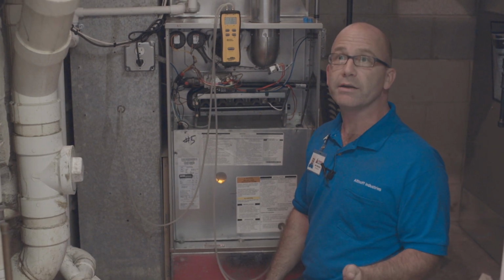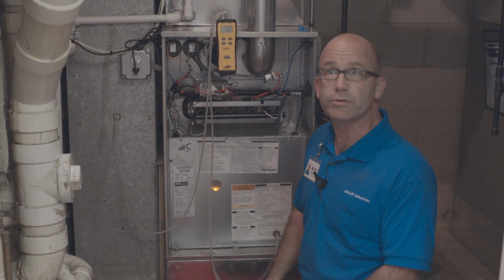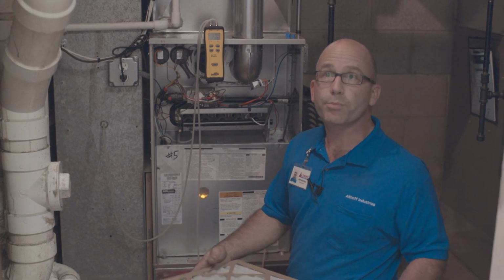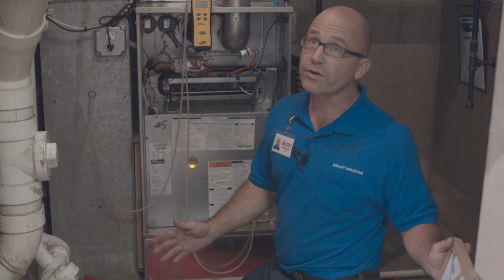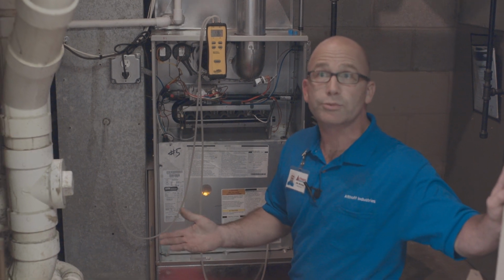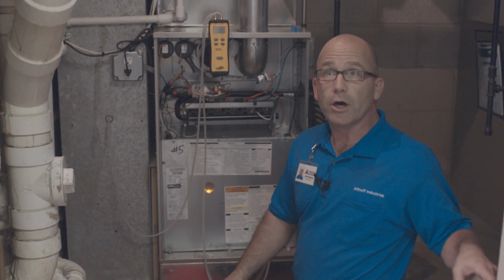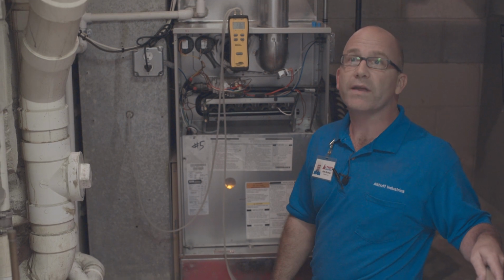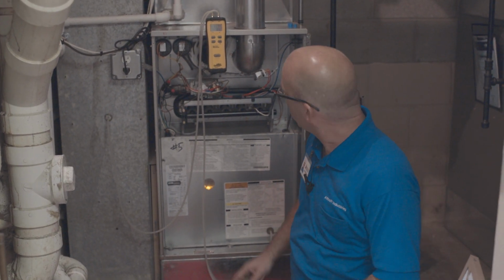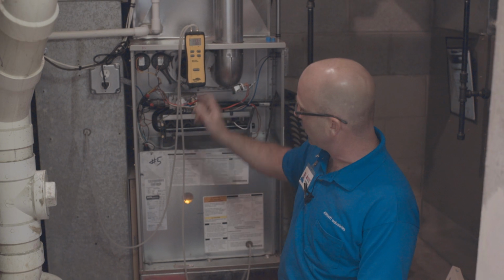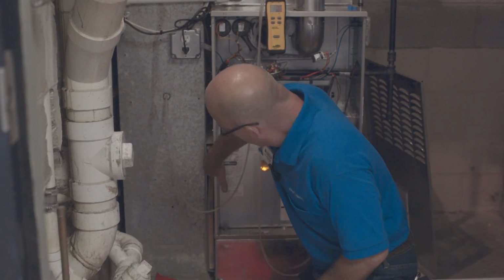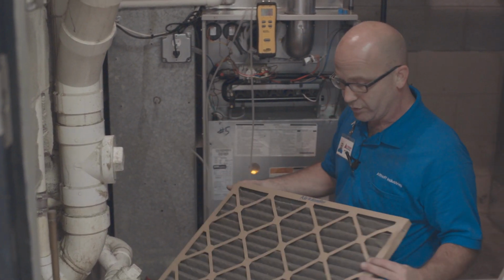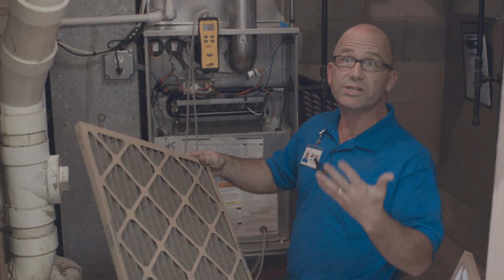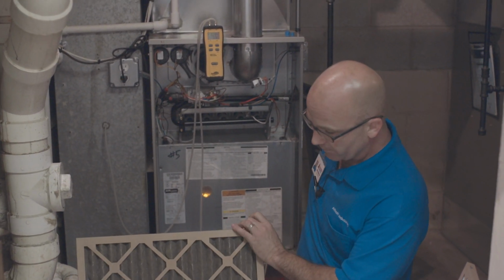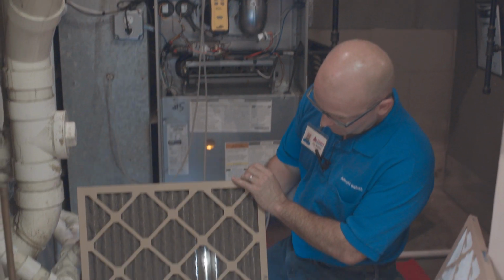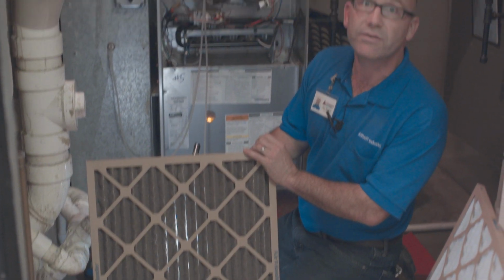So we recommend a standardized filter and just change it maybe once a month instead of going the pleated route. If you have perfect ductwork, meaning perfect static pressure, which most people do not, you can go with a pleat. But we find that most people don't. So this number is at 1 inch right there on the filter. And as you can see, if you were to hold this up to the light, you can't even see light through it. That's how plugged up it is. As a matter of fact, when I put my flashlight on this, you can barely even see the flashlight through it, you know?